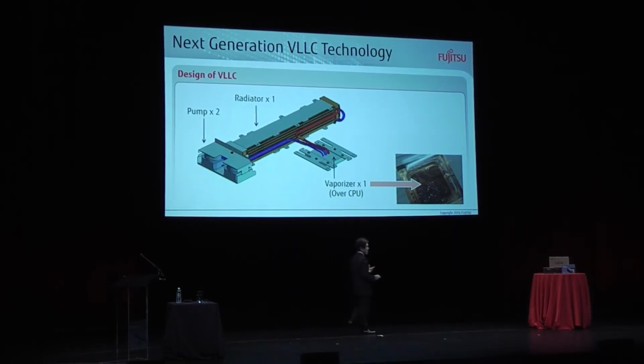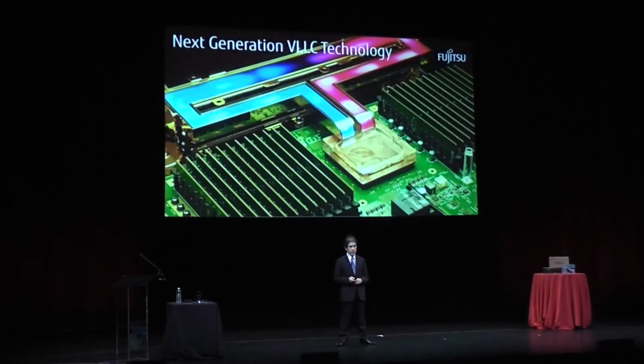The mechanism looks simple. We put a part called a vaporizer over each CPU and let it boil and vaporize water. Much heat is taken away in this process, and we keep the boiling temperature much lower than that of the atmosphere - 122°F or 50°C - by lowering the pressure inside the vaporizer. So it's high-tech, it's not as easy as it looks.